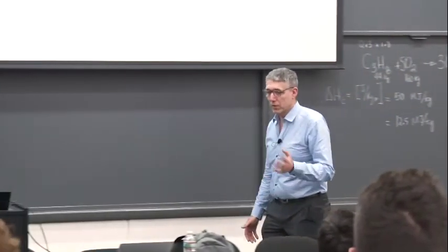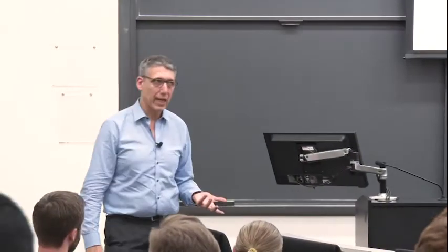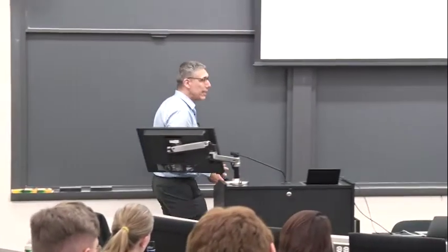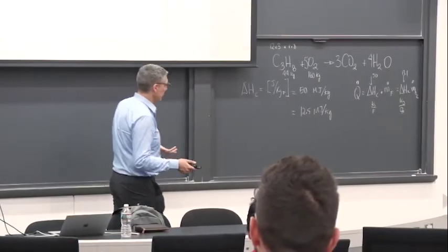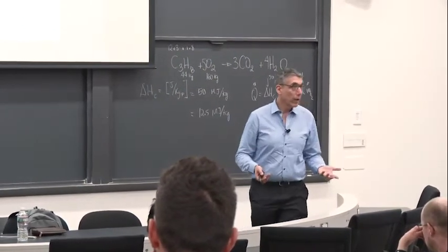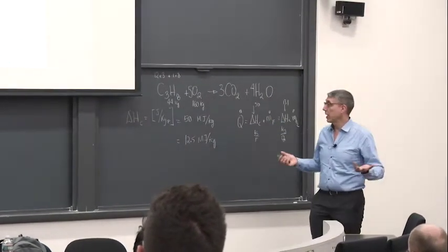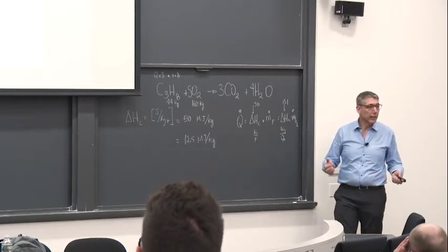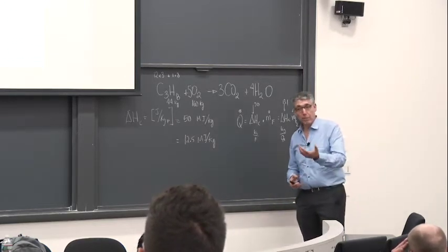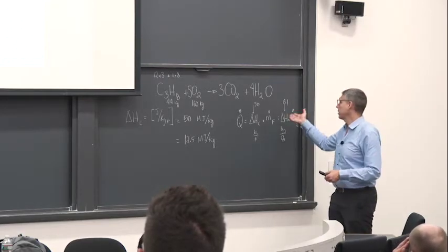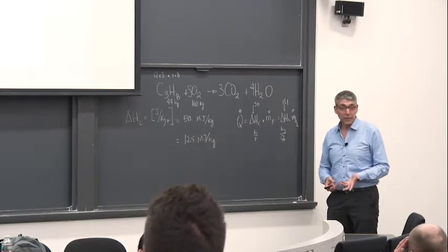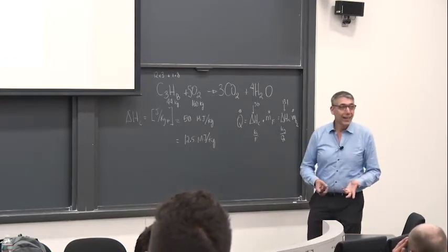There's been so much said about the cone calorimeter and oxygen consumption calorimeter as a means to obtain a more precise estimate of the heat of combustion. And that is actually not the case. All it is is an assumption that effectively leads us to exactly the same place, which is the fact that it is the heat of complete combustion. And I can repeat this for all of them, and it will get me exactly the same place. Plus or minus a little bit, this will all circle around that value of 13. Effectively, it is more or less an approximation of the complete heat of combustion if expressed as a function of kilograms of oxygen consumed. Is that okay? Have I disappointed you? So that's all it is.